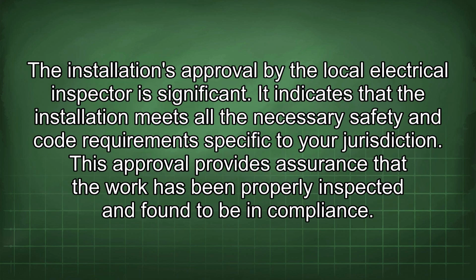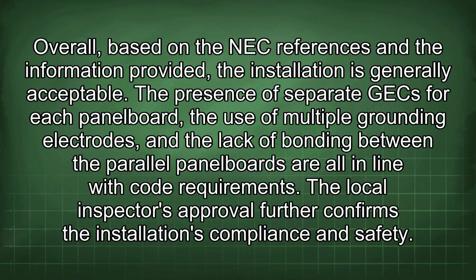The installation's approval by the local electrical inspector is significant. It indicates that the installation meets all the necessary safety and code requirements specific to your jurisdiction. This approval provides assurance that the work has been properly inspected and found to be in compliance. Overall, based on the NEC references and the information provided, the installation is generally acceptable. The presence of separate GEC for each panel board, the use of multiple grounding electrodes, and the lack of bonding between the parallel panel boards are all in line with code requirements. The local inspector's approval further confirms the installation's compliance and safety.